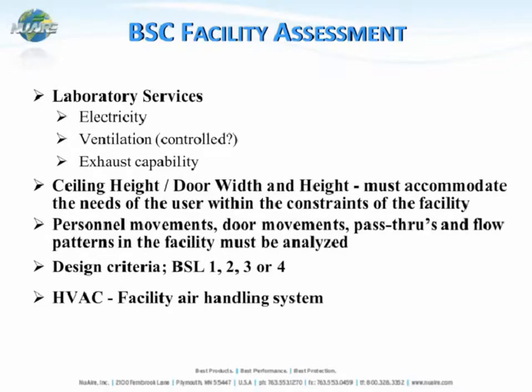Once you take all of the risk factors into account, you can start a BSC assessment for the facility. The first things to look at are laboratory services: what electricity is required to run the product, is ventilation in the lab appropriate, and do you need to exhaust the biological safety cabinet to the outside if you're working with something volatile? Also take into account ceiling height to make sure the unit will fit and can work at the required work surface height, and measure doorways to ensure getting the equipment into the lab space will not be an issue.